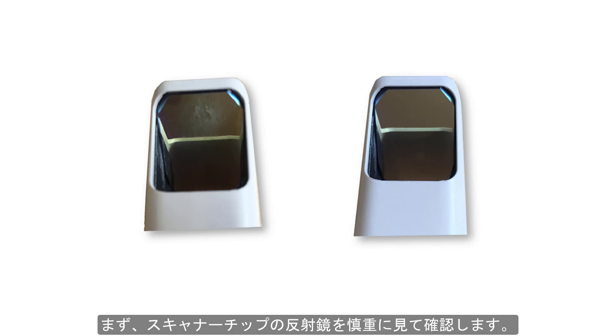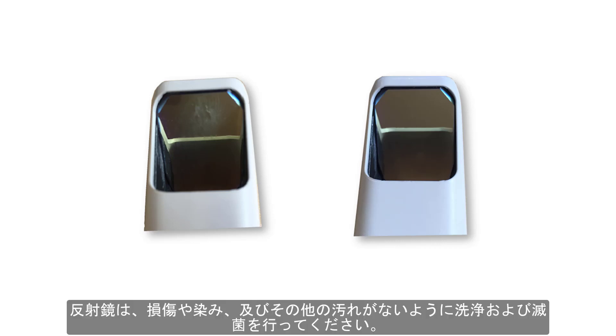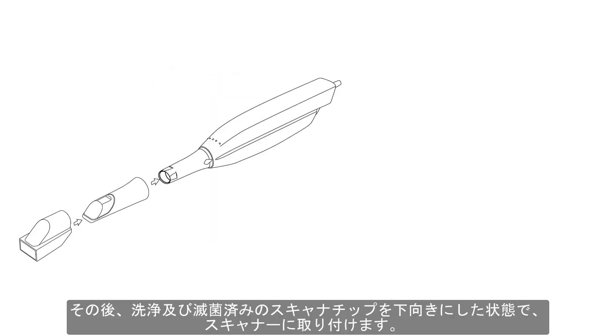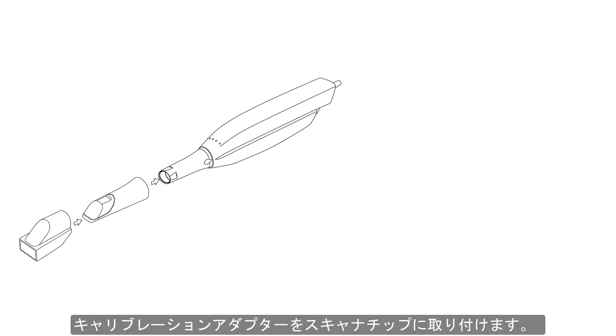First, carefully examine the mirror of the scanning tip. The mirror must be cleaned and sterilized, free of scratches, water stains, and dirt. Afterwards, attach the tip to the scanner facing downwards and put the color calibration adapter onto the scanner tip.